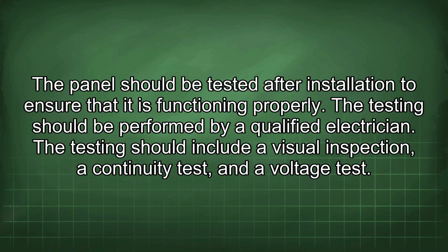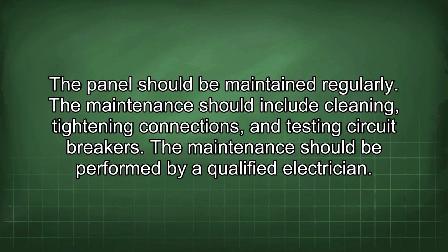The panel should be tested after installation to ensure that it is functioning properly. The testing should be performed by a qualified electrician. The testing should include a visual inspection, a continuity test, and a voltage test. The panel should be maintained regularly. The maintenance should include cleaning, tightening connections, and testing circuit breakers. The maintenance should be performed by a qualified electrician.